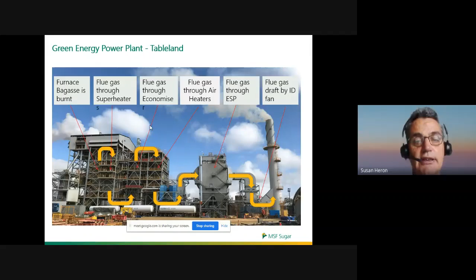We basically went from a 19 bar boiler up to an 87 bar boiler, and from a 7 megawatt back pressure turbine to a 24 megawatt extraction condensing turbine. With the grid connection upgrade, we needed to go from being able to put potentially up to about 3 MVA out the door to being able to put 20 MVA out the door, so that we could export our 17 megawatts.